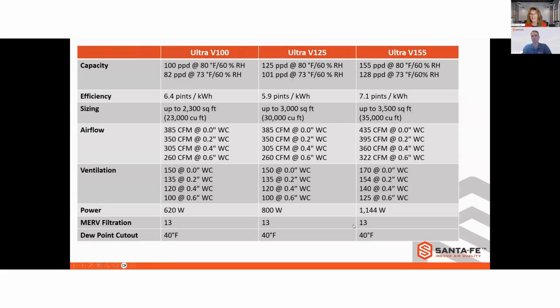So diving into the data about these units here, you can see at the capacity on top, we always give you the 80-60, but then we also give you the DOE rating of 73 degrees and 60% relative humidity, which is very important to know when you are sizing dehumidifiers for applications, to be more realistic about what's the true capacity that you're going to get at those different temperatures and RHs.